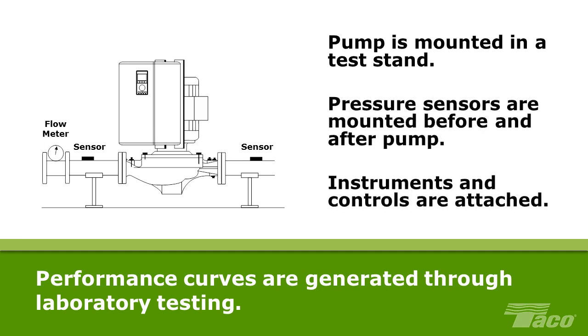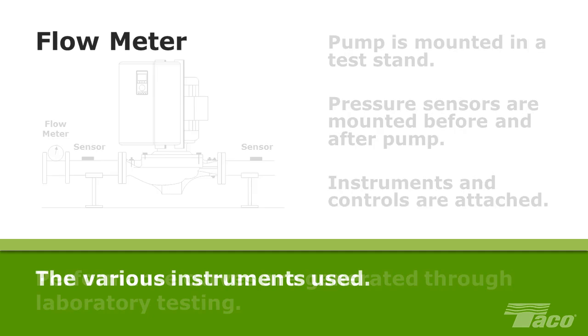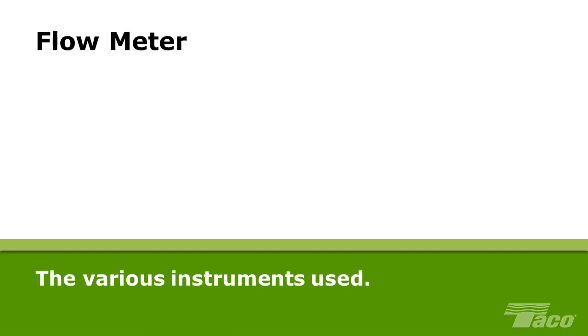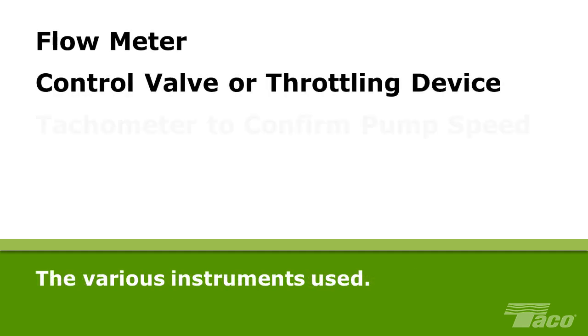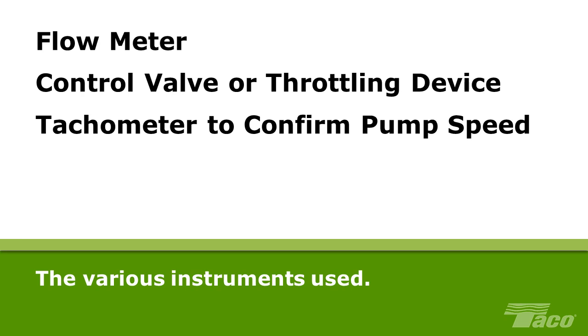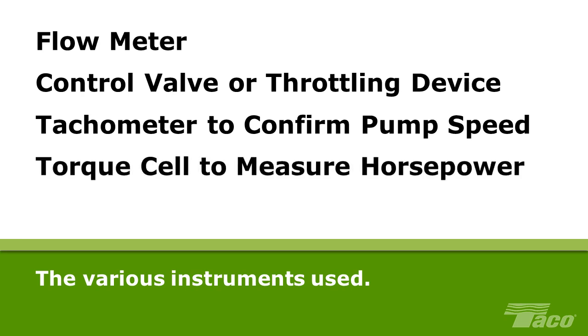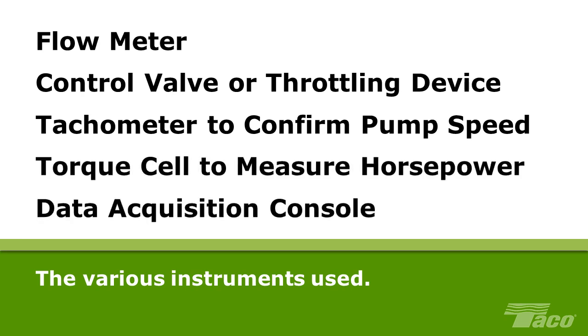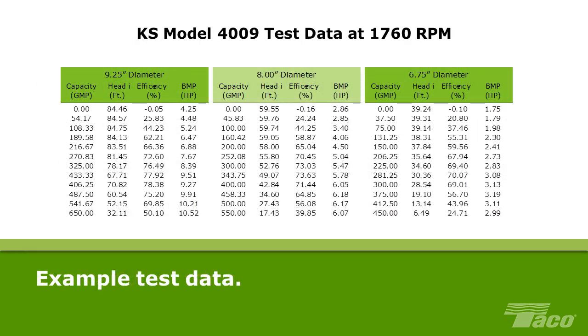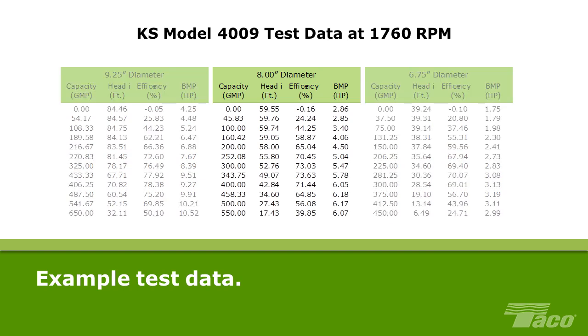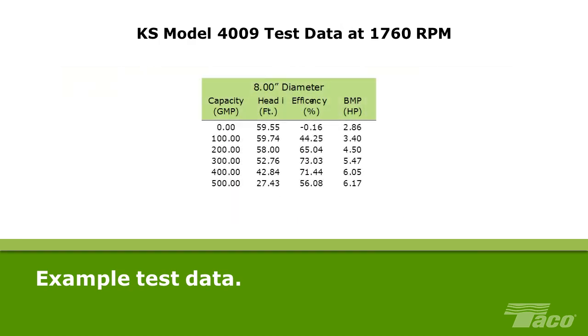Then various instruments and controls are attached. A flow meter, a control valve or throttling device, a tachometer to confirm pump speed, a torque cell to measure horsepower, and a data acquisition console. The pump is then placed into operation. Here's example test data from a Taco KS pump tested at 1,760 RPM. For simplicity, we'll focus on just one impeller diameter, 8-inch, and 6 operating points.